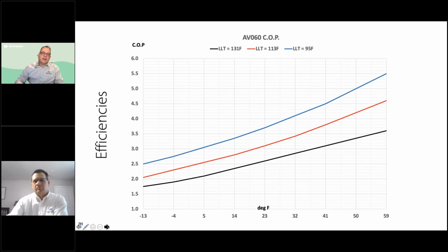Efficiencies are great. This slide shows the efficiencies from -13, which is where that unit can run down to and then shut off, all the way up into the 50s. You can see here, we have 3 different lines. The blue line would be our typical radiant floor temperatures. They might be lower than that with outdoor temperature reset, but just as a gauge, even at -13, our COP is still 2.5. When you're doing domestic hot water heating, the black line, even at that minimum temperature, is still around 1.8 COP. So it's literally twice as efficient, even at the coldest temperatures, than an electric water heater.